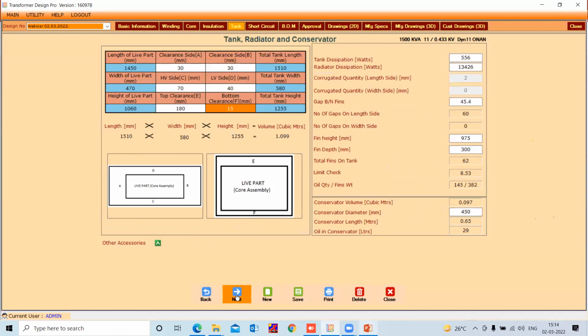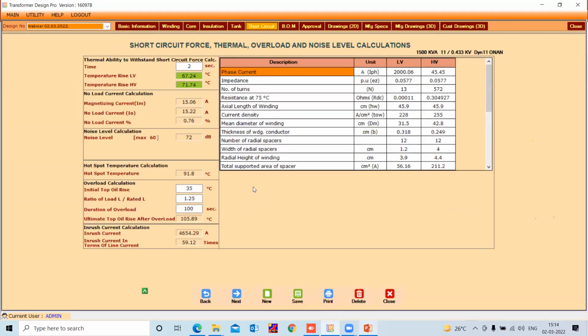Now, I will take you to the quality card of this transformer. The short circuit details are available over here. Firstly, the thermal ability to withstand short circuit forces calculation. The duration and temperature rise for LV and HV are given over here. And based on the time duration, your temperature value will get changed over here.